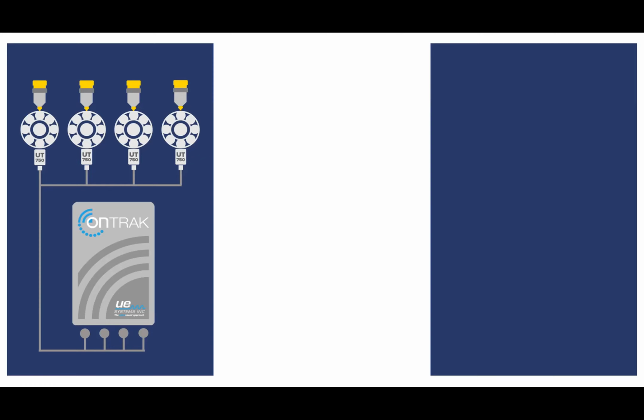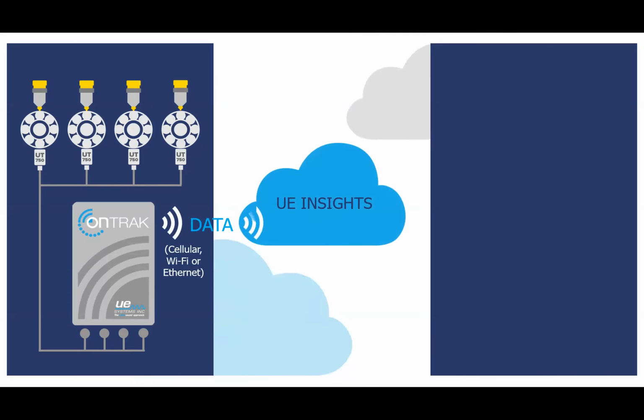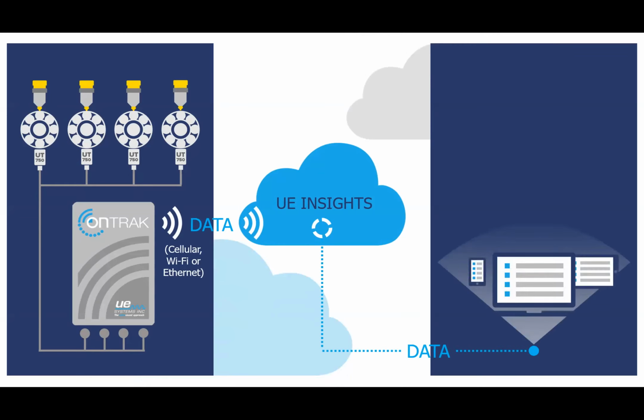That 750 sensor is monitoring the friction in that bearing. That's essentially what we're trying to do with the bearing. Friction tells us when we need to lubricate, and friction tells us the health of that bearing. So it's monitoring that, and the OnTrak is capturing that data, and it's going to send that data out either cellular, Wi-Fi, or Ethernet to UE Insights. UE Insights is turning that data into insights, looking for: do I need to lubricate? Do I need to do other things to help prevent failure of this bearing?